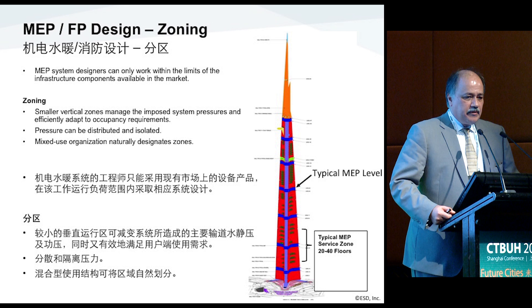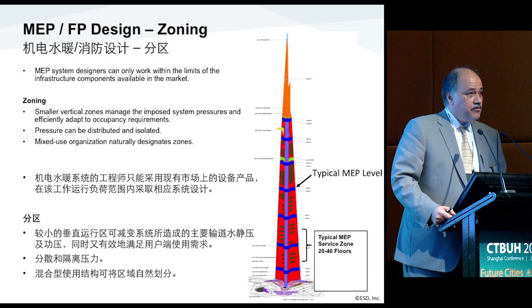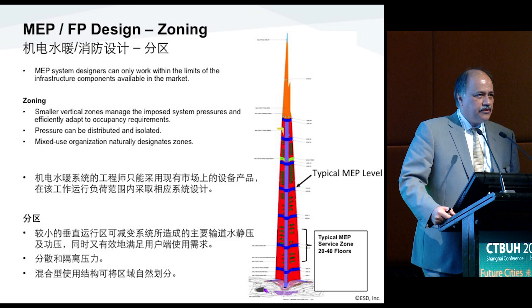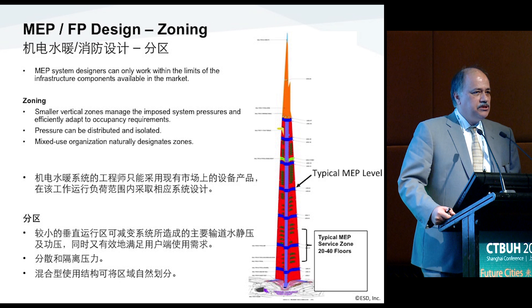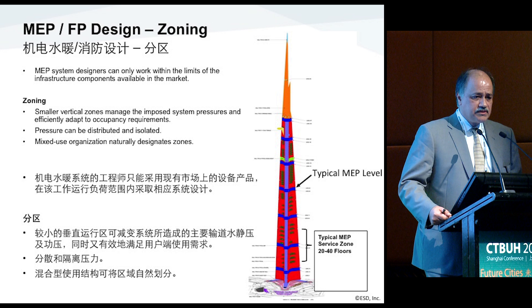This building has seven primary mechanical levels. They are two-story spaces configured to serve roughly 20 to 30 floors each — a small grouping per level. They are also overlaid with the occupancy of the building to accommodate the required metering and sub-metering, and operationally they allow isolation of parts of the building without affecting the rest of the systems.